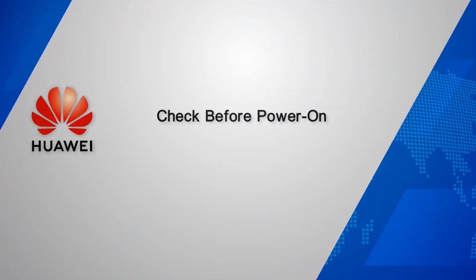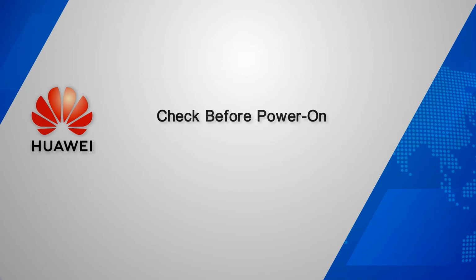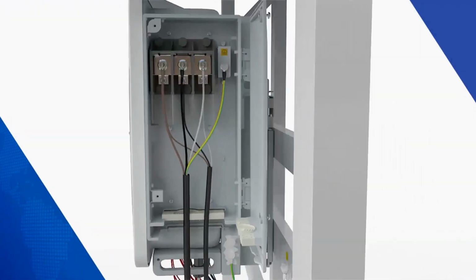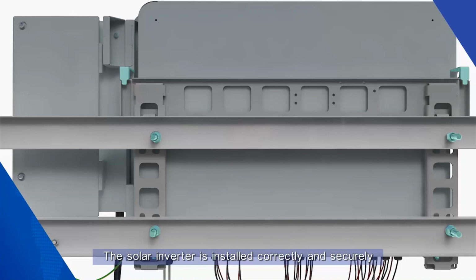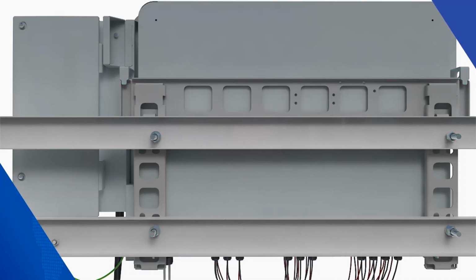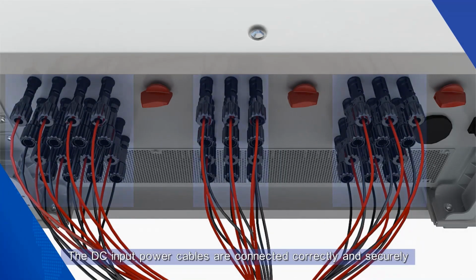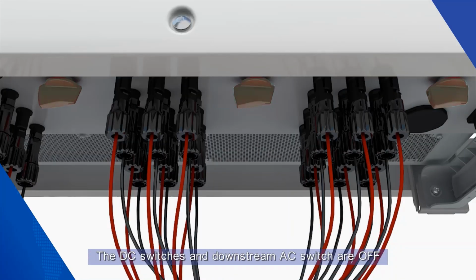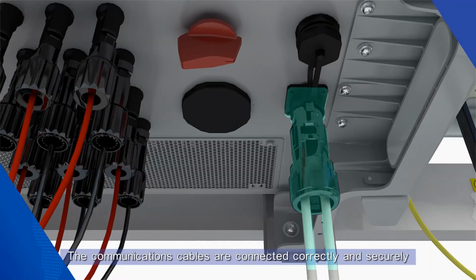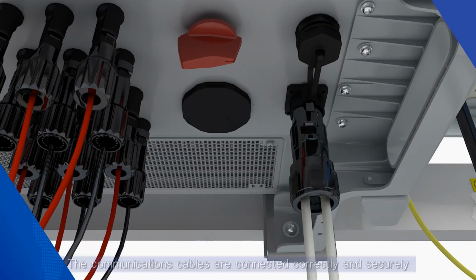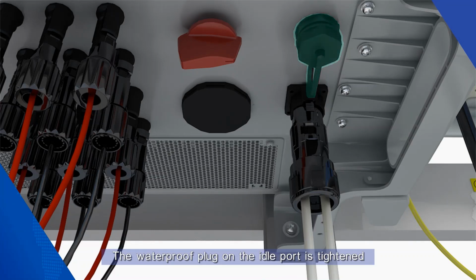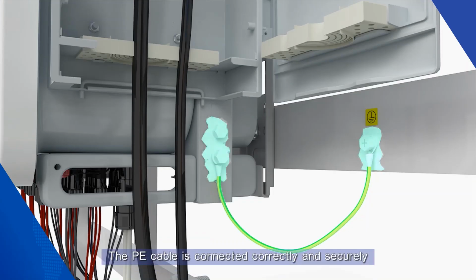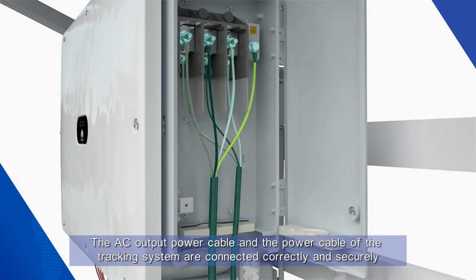Check before power on. The solar inverter is installed correctly and securely. The DC input power cables are connected correctly and securely. The DC switches and downstream AC switch are off. The communications cables are connected correctly and securely. The waterproof plug on the idle port is tightened. The PE cable is connected correctly and securely. The AC output power cable and the power cable of the tracking system are connected correctly and securely.